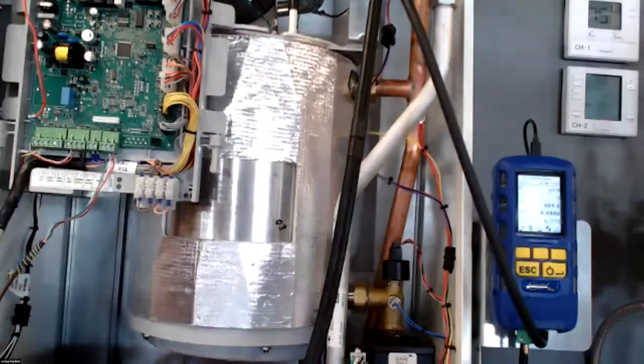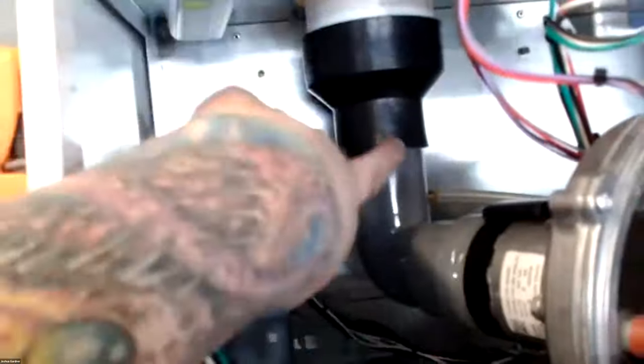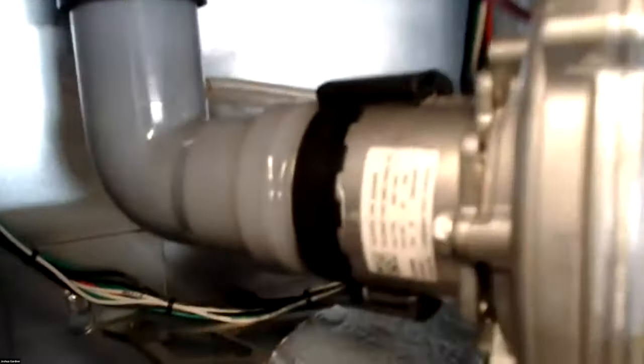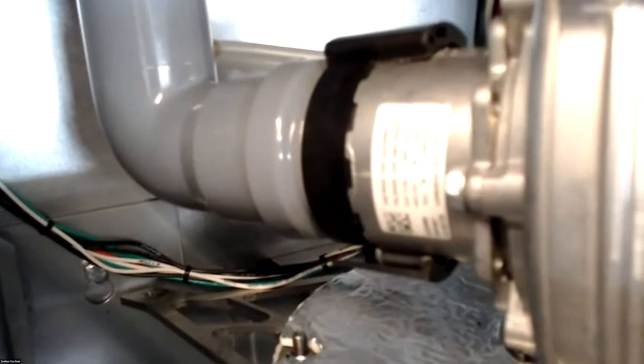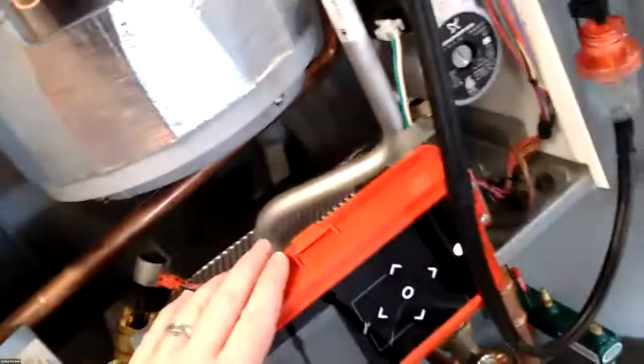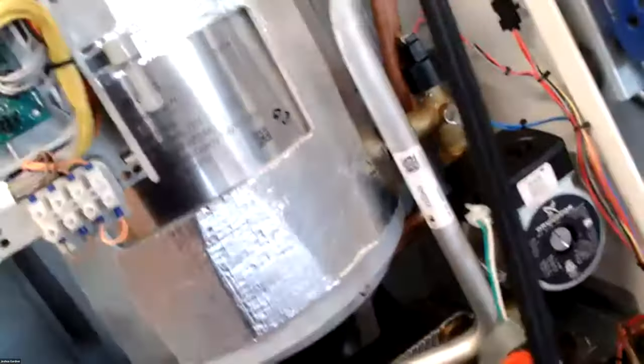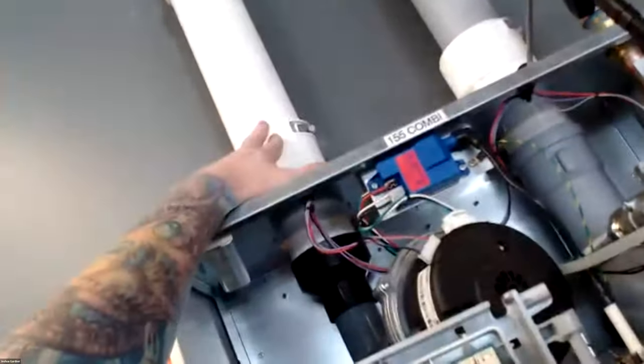You'll take off this inlet boot, remove that venturi, put the new venturi on, and then put this intake boot back on. Mechanically, that's the only thing you have to do for the conversion. Then you just change the appliance setting. And if it's a 110 or 155, you add that second piece of foam on the intake. Ah, got it. Okay.